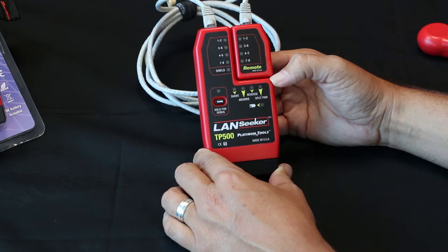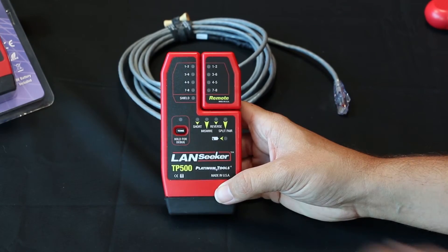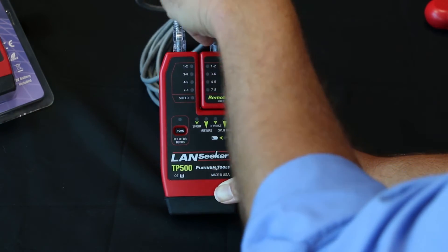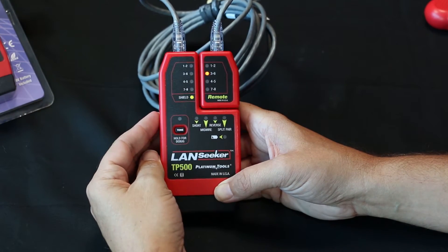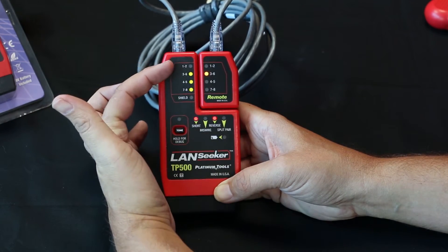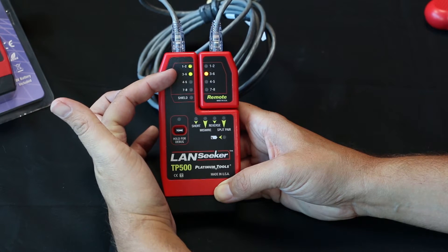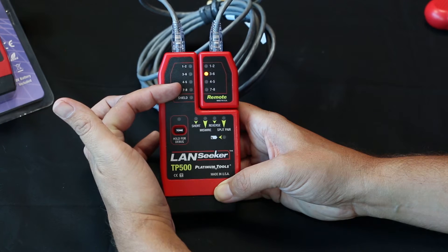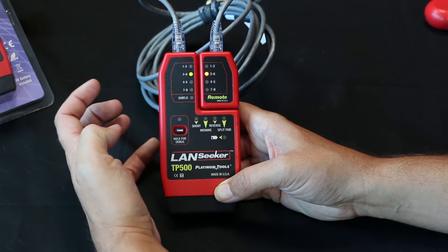Now let's see a bad cable. Let's try this next cable on the LANSeeker. Connect it into the remote. Right away we're seeing there is an open on one and two. Looks like three and six are good, and there's a fault on four and five, and seven and eight. And there's a short and a reversal.